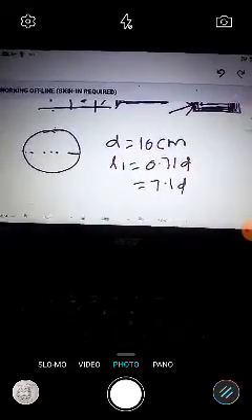If you have two dimensions, it is a two step core. Now let us see how we can do it for two steps. For the second step we take a dimension. The dimension is, as we have seen, 10 centimeters. The first one we calculated with 0.71, for 10 centimeters diameter, which gave us 7.1 centimeters, through which we draw a single step.